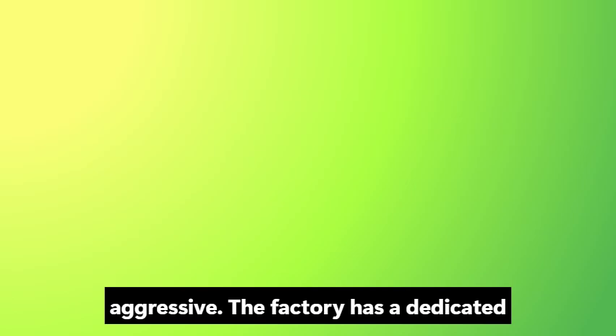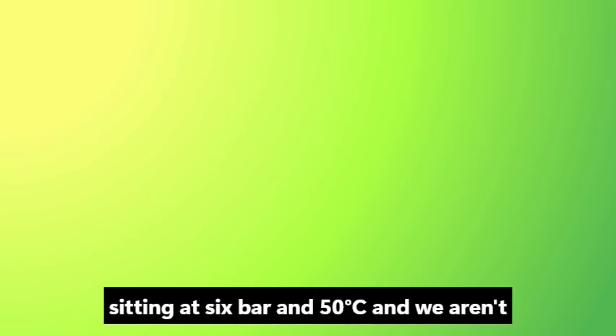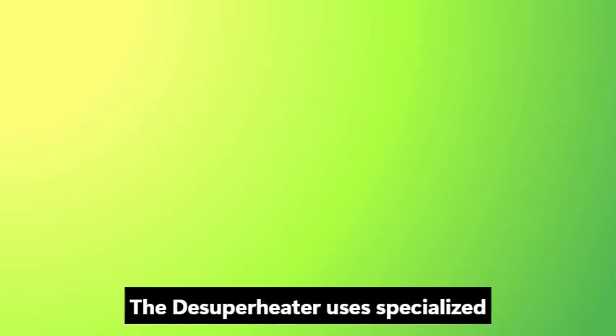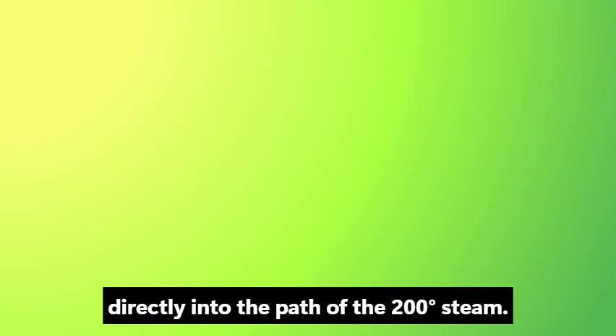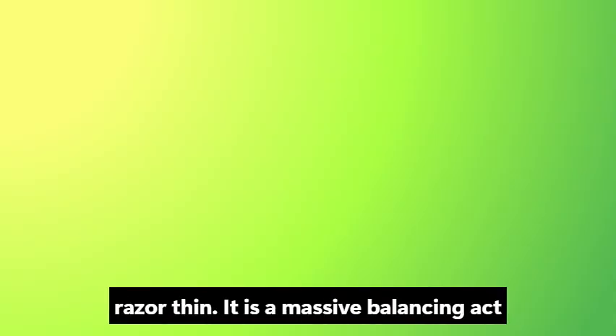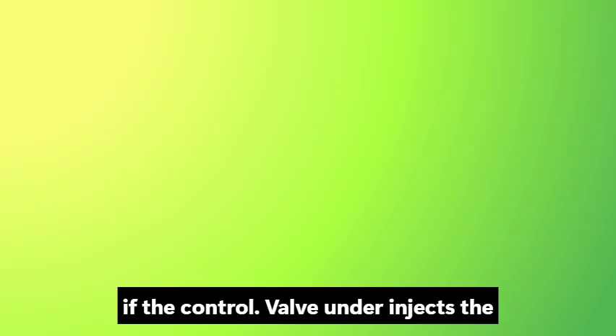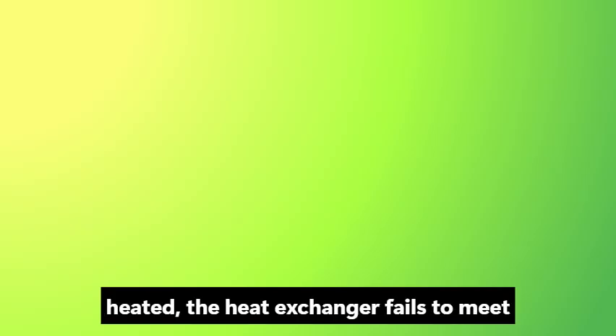Right. The factory has a dedicated supply of pressurized liquid water sitting at 6 bar and 50 degrees Celsius. And we aren't just pouring it in like from a bucket. The desuperheater uses specialized nozzles to highly atomize that 50-degree cooling water. Spraying a fine mist directly into the path of the 200-degree steam. Exactly. And the margin for error here is razor thin. It is a massive balancing act. If the control valve underinjects the cooling water, the steam remains superheated, the heat exchanger fails to meet the process load, and we damage the reactor.